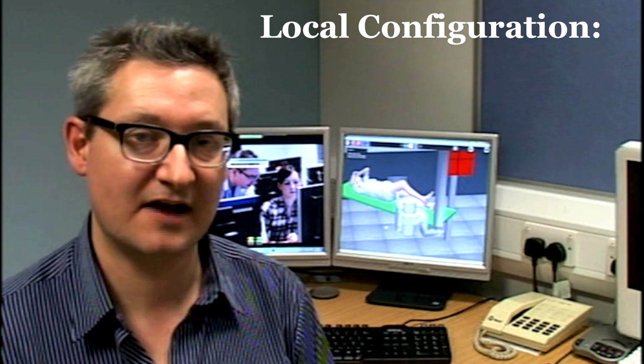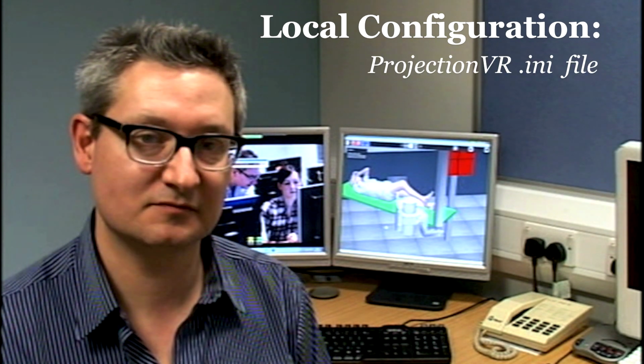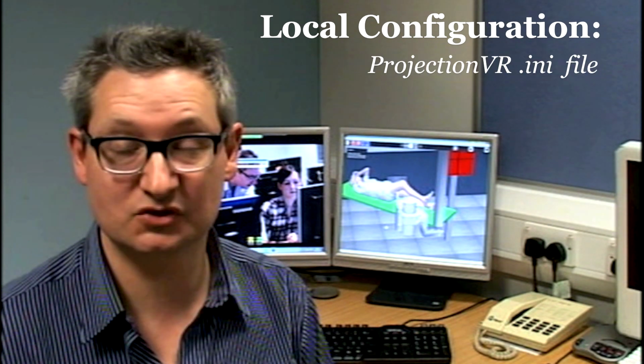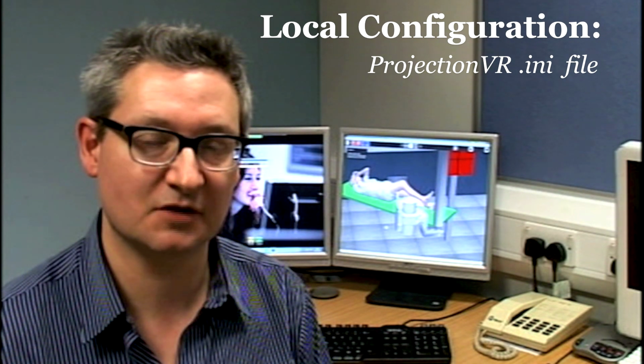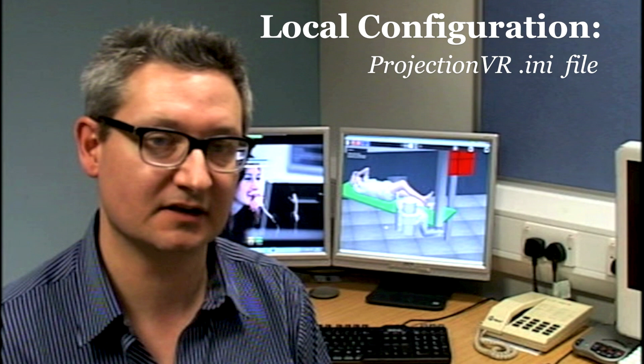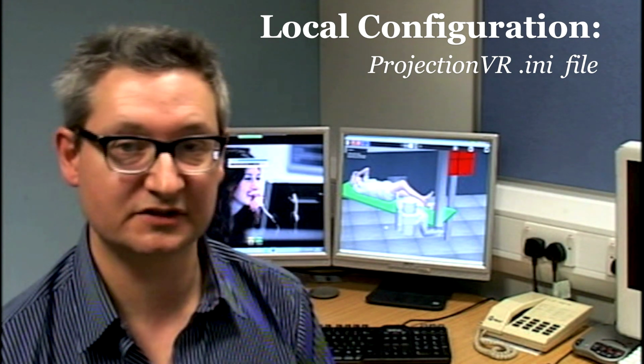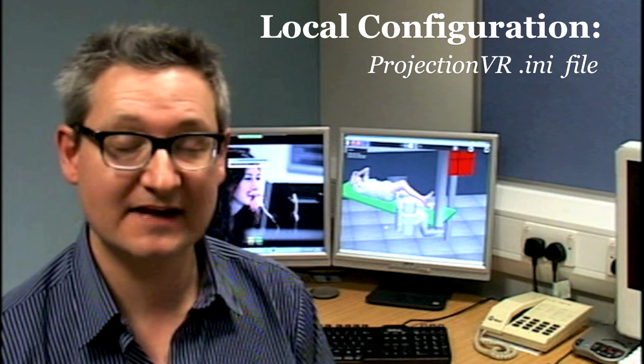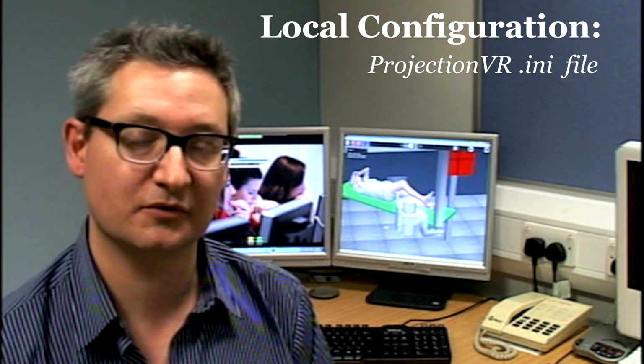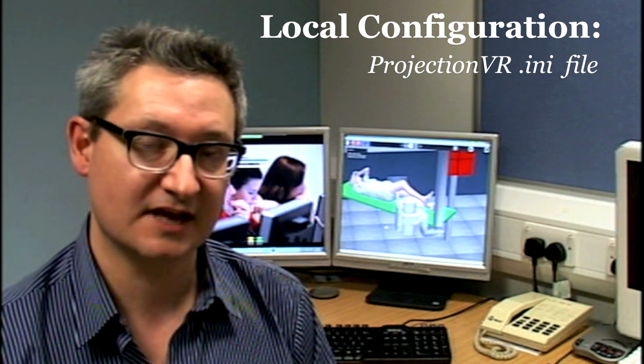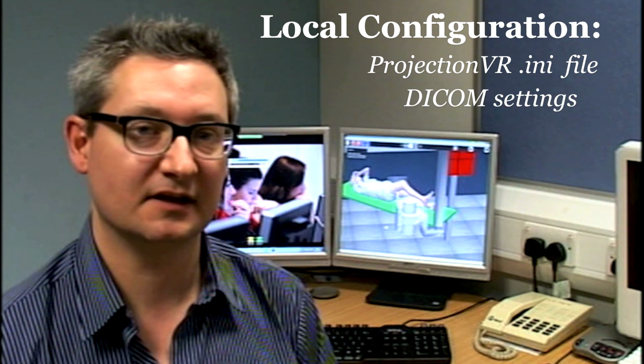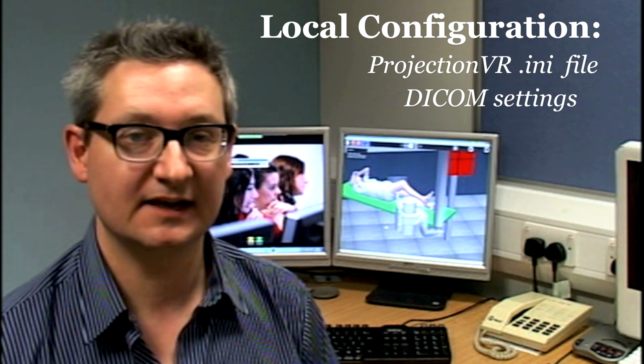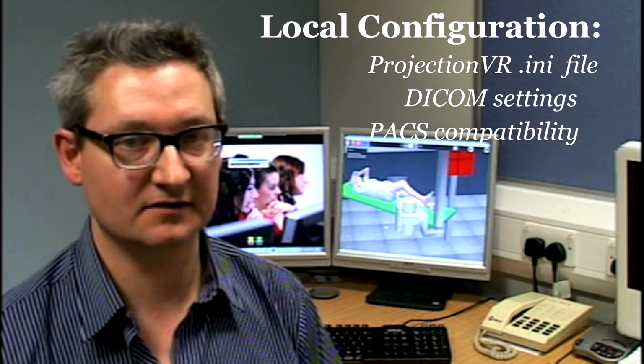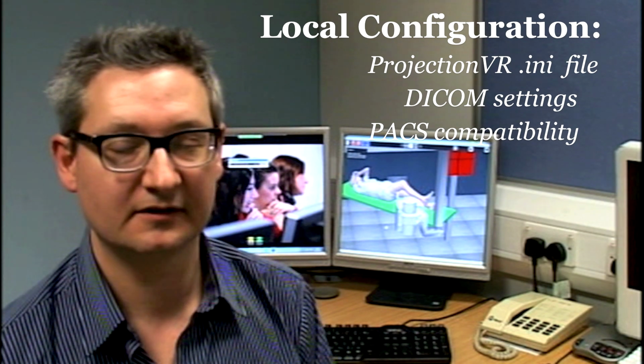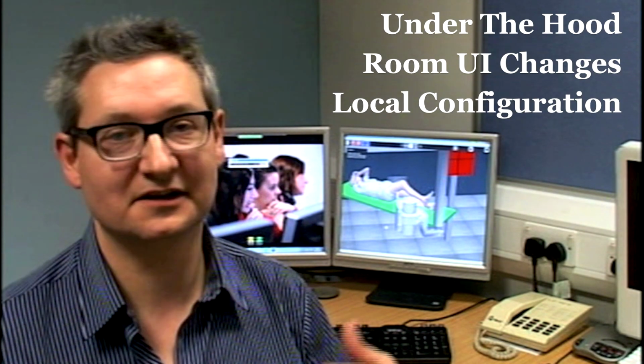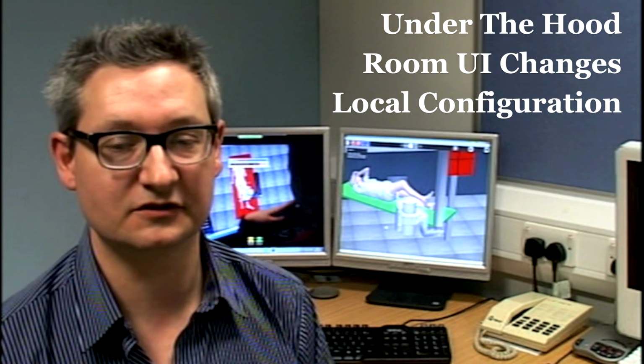Talking of configuration, we have a file which you can put settings in when you install the software, and the software will pick those changes up and it will work that particular way for your particular environment or your particular university. And we've added new settings in there that you can change. So for example, you can change the way the DICOM is saved and where it's saved. You can put the root of the directory that you want it to save in that config file, and that will allow you to get it uploaded to a PAC system. So these are all small little changes that have made quite a good difference.